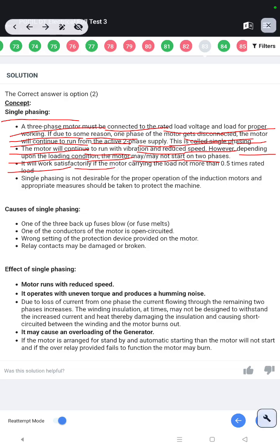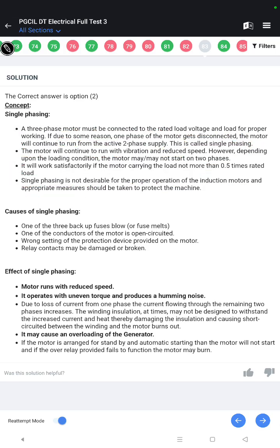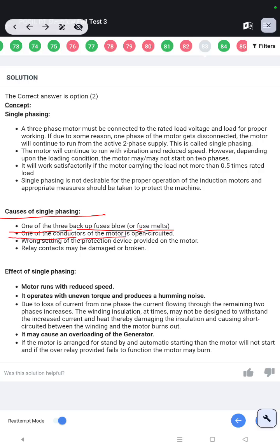It will work satisfactorily if the motor is carrying a load not more than 0.5 times rated load. Single phasing is not desirable for the proper operation of the induction motors, and appropriate measures should be taken to protect the machine. Causes of single phasing: one of the three backup fuses blows or the fuse melts. One of the conductors of the motor is open circuited. A wrong setting of the protection device provided on the motor, or the relay contact may be damaged or broken.